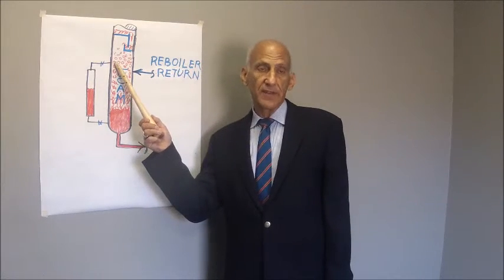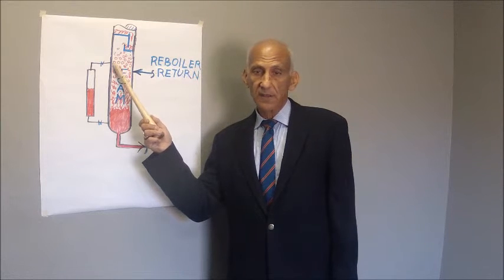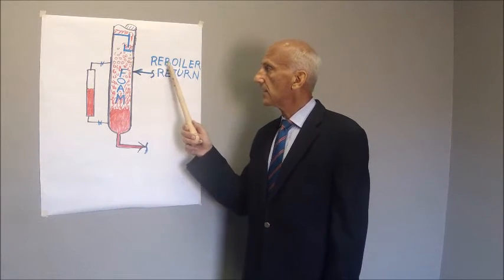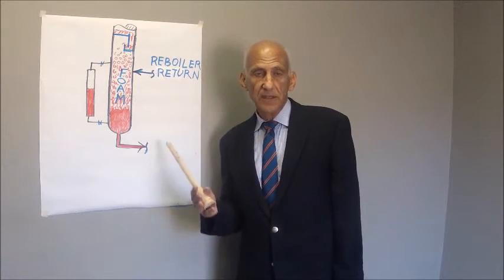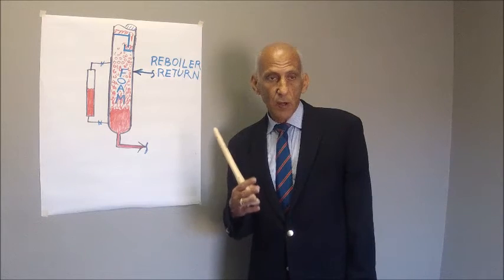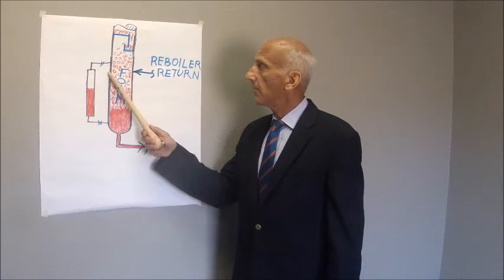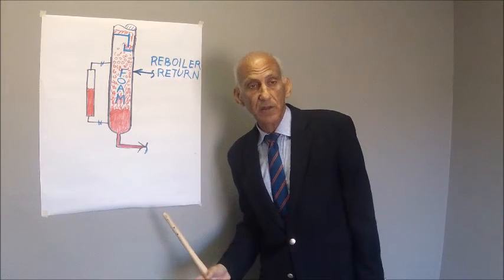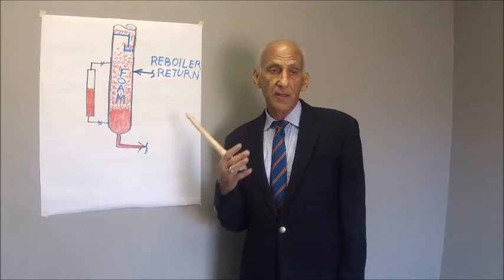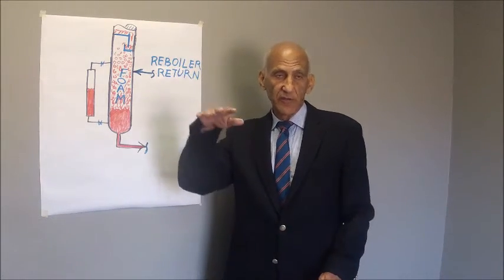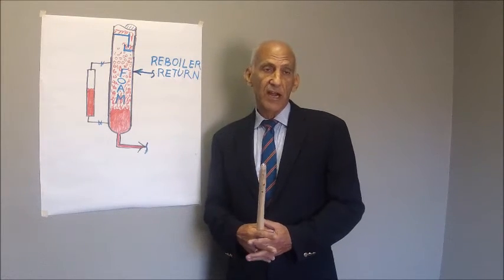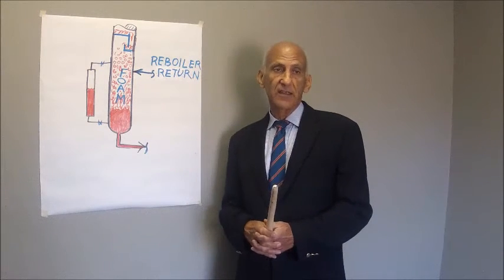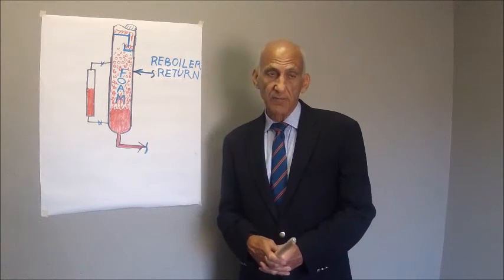Once the foam rises above the top tap, you could still only have half of the gauge glass full of liquid, but having the foam rise above the reboiler return or vapor inlet nozzle means the force of the vapor blowing below the foam level will blow the foam up into the bottom tray. Once the foam is blown into the bottom tray, the bottom tray is going to flood and then the flooding will progress up the tower. I call this very common problem foam-induced flooding. Again, let me remind you that the level you see in the tower is normally not represented by the level in the glass.